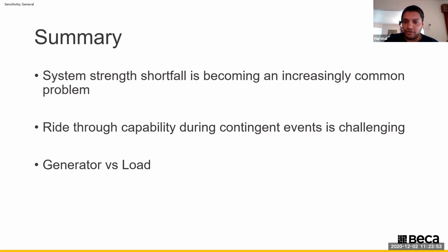Demonstrating continuous uninterruptible operation in response to contingency events is also challenging, because network service providers dictate the number of contingency scenarios, and it's becoming increasingly more complex due to a number of other committed generators that you need to factor in when doing system studies.